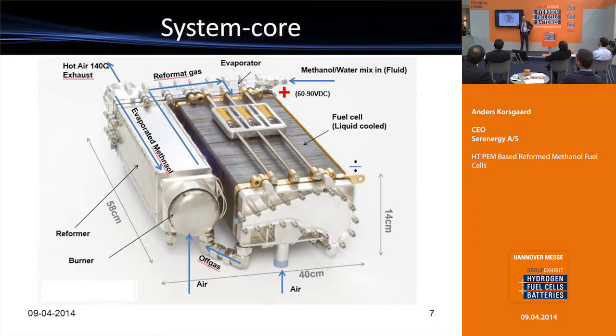It's being evaporated by the use of the heat produced by the fuel cell. We are taking advantage of the high operating temperature of the fuel cell to actually evaporate the water and the methanol. This can also be done with other systems, such as for natural gas, but you need quite a lot of water. So you take that thermal energy requirement off the reformer and let the fuel cell do that job. That gives you quite a few efficiency points, and that's the whole trick about why high temperature PEM is much more efficient than any low temperature PEM technology in this way.